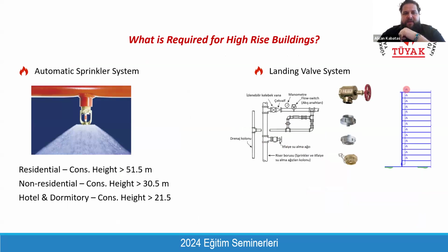When the building is becoming high-rise building, the automatic sprinkler system and landing valve system and another system that we will talk about are becoming mandatory and should be provided within the building. And both the main technical rooms and the existence of this system within the floor, especially on the ceiling, will affect your architectural coordination and design. And it is better for architects to understand what we will have while we are designing the building. Otherwise, you will become aware when the MEP designer submitted their drawings, but it will be too late to coordinate them. It will cause you a problem to find place and locate these additional systems.